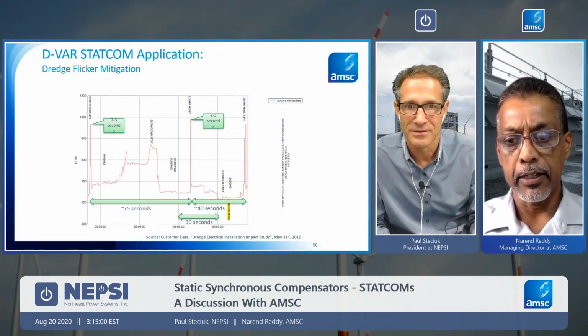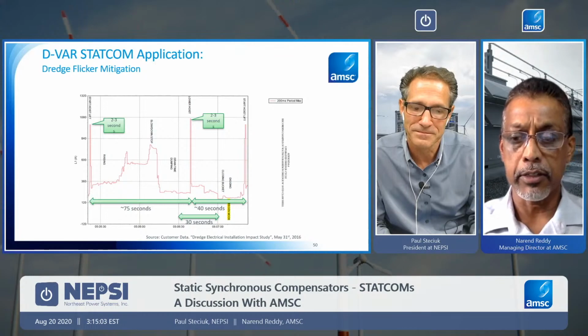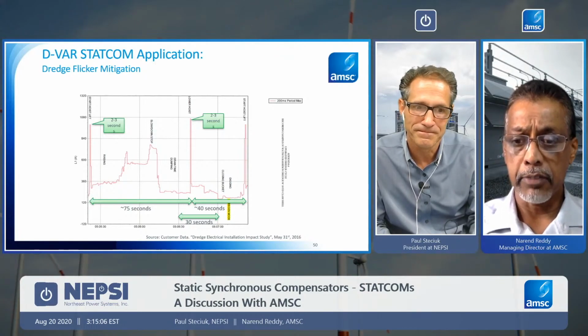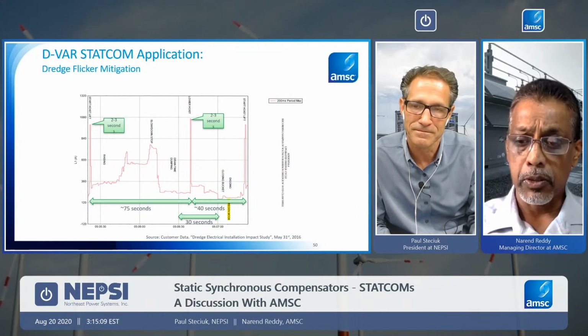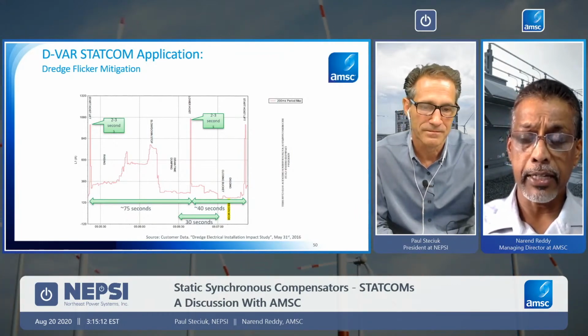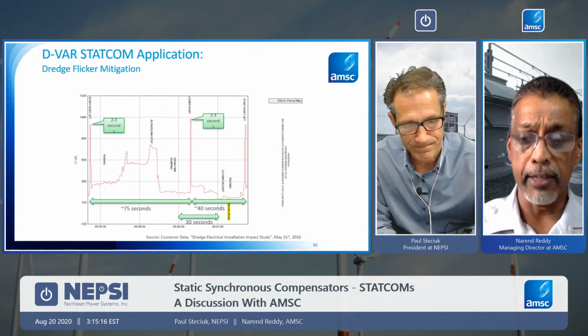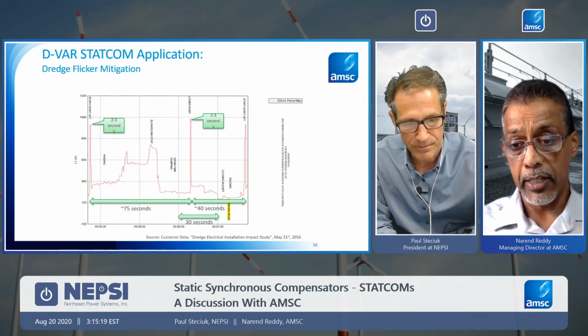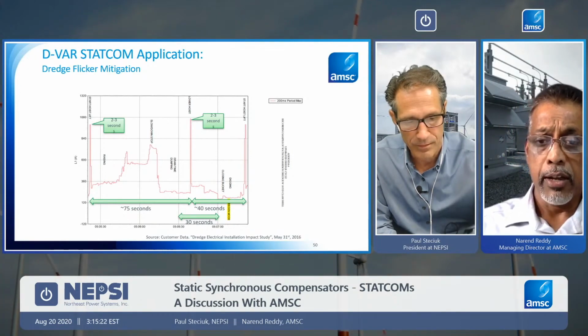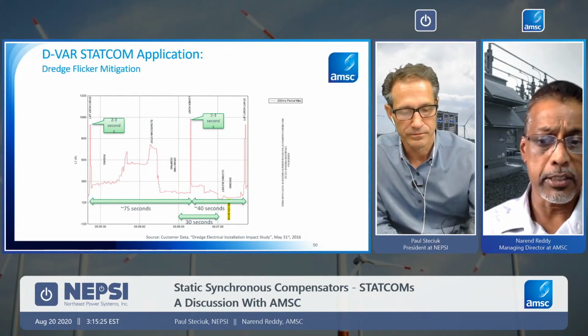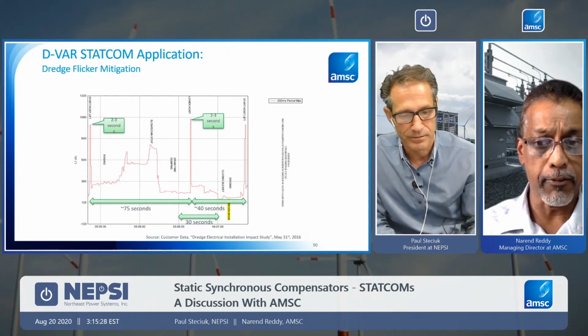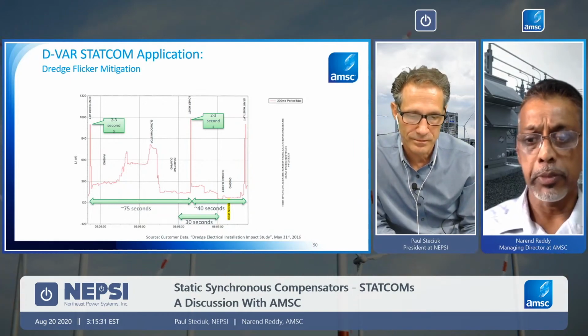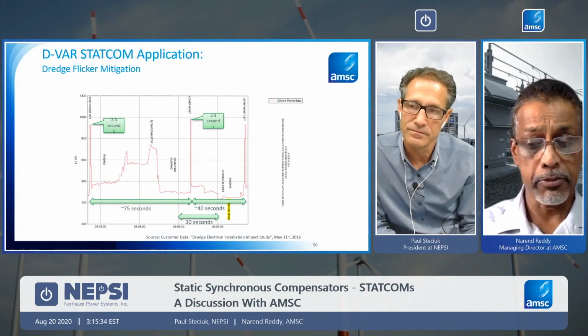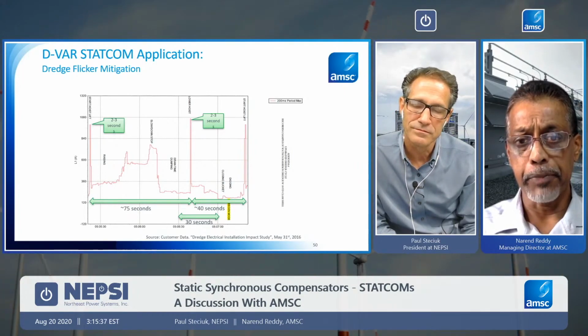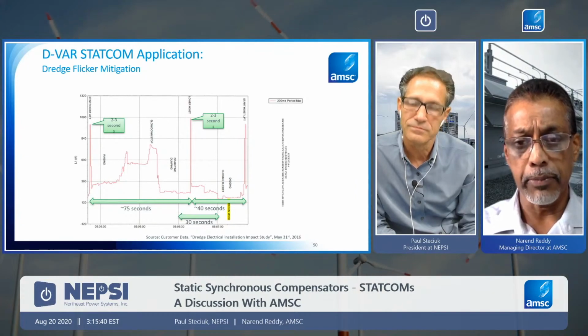Yeah, actually that is an important point. Flicker is not necessarily always caused by the grid. You have small, medium, and large industrial facilities that could be causing flicker back into the grid, causing disturbances for other customers as well. They might be causing a lot of harm to their own operations too in some cases. So absolutely. As I mentioned, the D-VAR STATCOM systems are configurable. They can be sized anywhere from 2 megavars to tens of megavars in capacity, so they're very deployable for small applications as well.